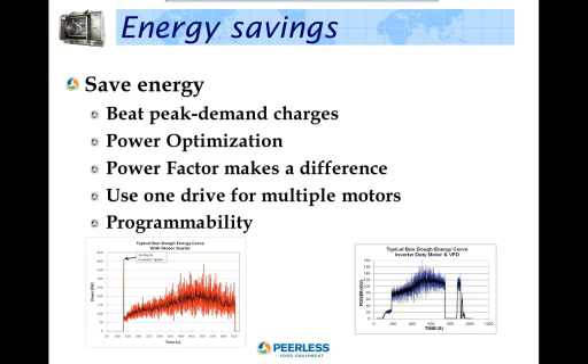Power factor makes a difference. Power factor and how it affects displacement and harmonic distortion is another important consideration in drive selection. Drives that are near unity true power factor translate to reduced energy use. Use one drive for multiple motors. Synchronous transfer capabilities use one VFD to start multiple motors to reduce full load current and reduce energy consumption.